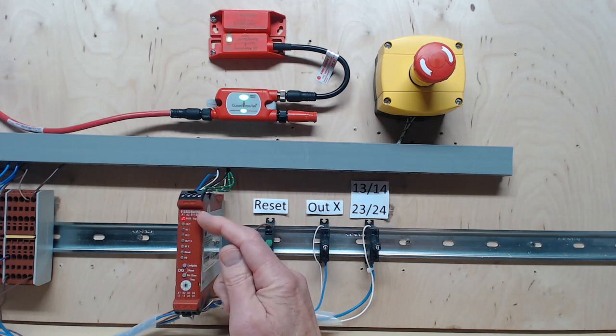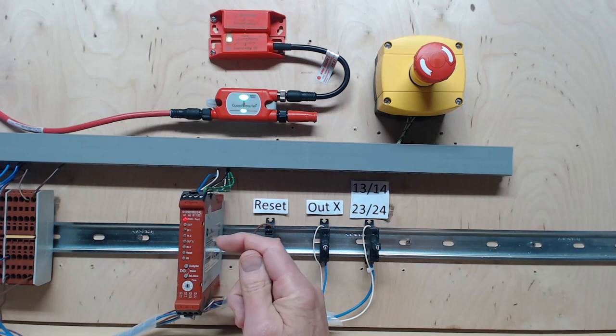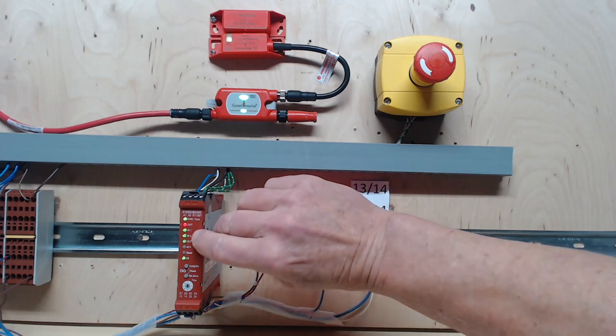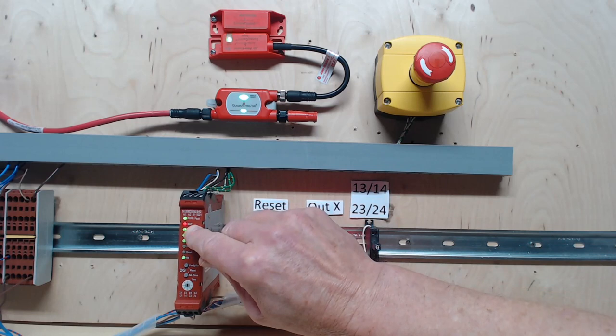The power fault indicator flashes green twice and then turns solid red. The DG relay is rebooting and applying the saved configuration. After restarting, the indicators show the operating status. You see the in one and in two indicators are green. The out indicator is red because we selected monitored reset on the output.